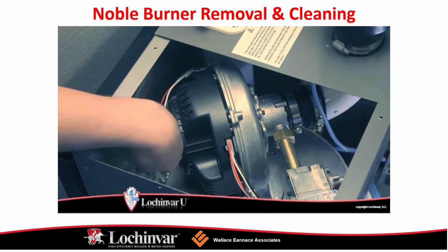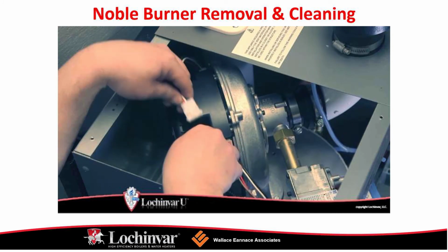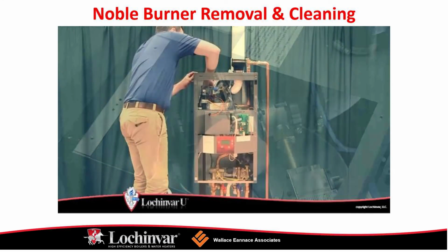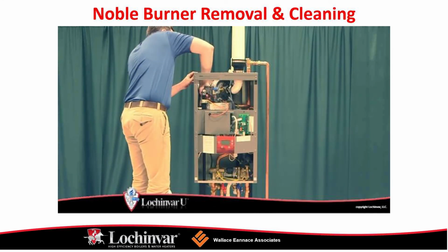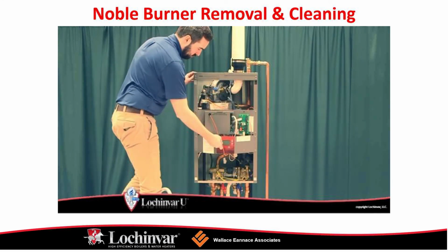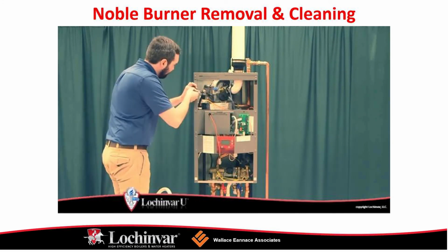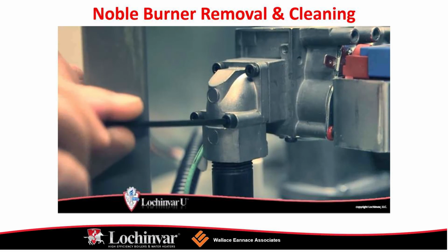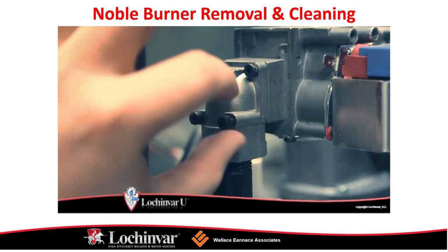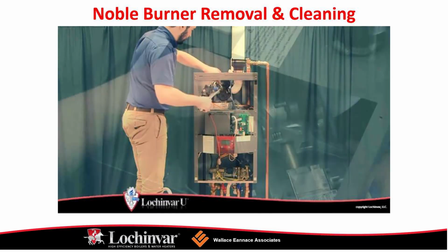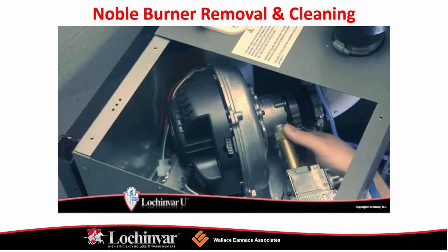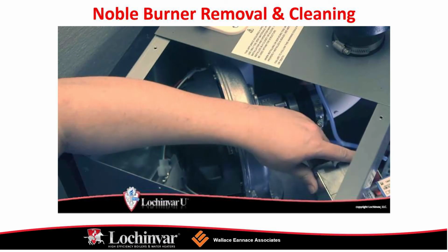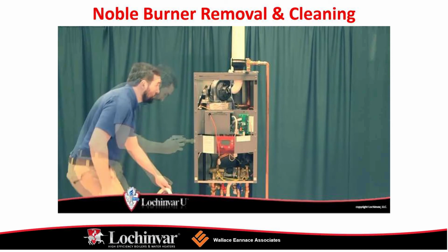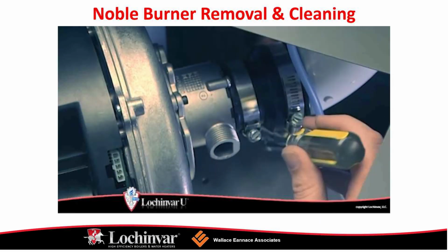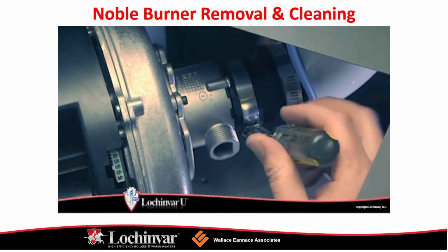The Noble has gained quite a bit of popularity over the last 4 years since it's been introduced to the market. It's a wall hung boiler only and a wall hung combination boiler water heater. Again, stainless steel fire tube design, great product, easy to service, easy to access, easy to install. Venting's a breeze. And so the next video touches on the removal and cleaning of the Noble burner.